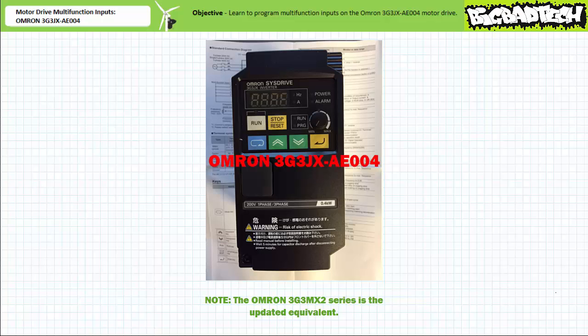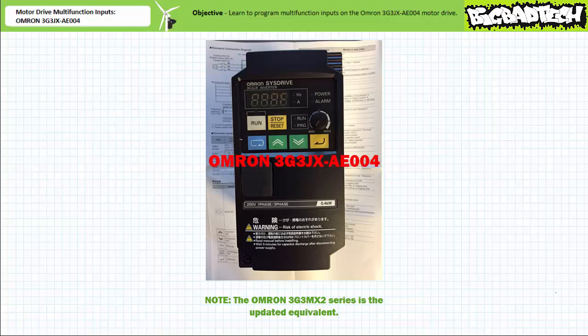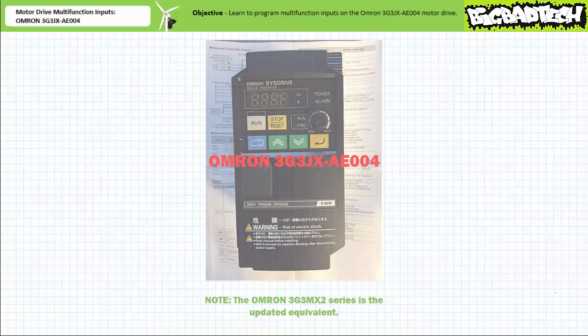Thus far we've been restricting our operation of the OMRON 3G3JX AE004 motor drive to the run and stop/reset button inside the digital operator group. The one exception to direct operation being the external speed potentiometer we configured in the installing a speed potentiometer lecture. If you recall, we installed a speed potentiometer and programmed the drive to recognize it rather than the frequency adjustment knob in the digital operator group using extended function parameter A001, frequency reference selection.